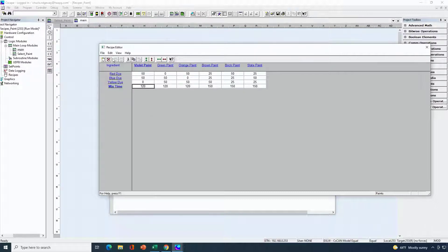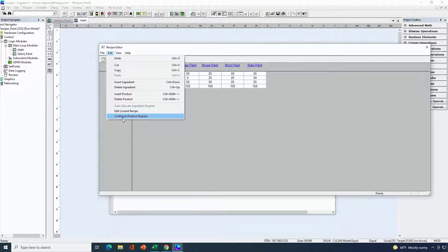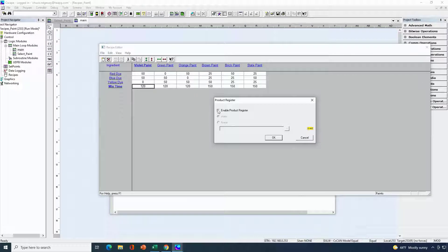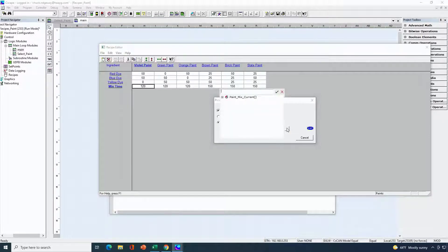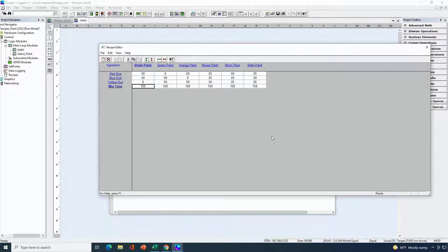One step I did a little out of order — let's go ahead and do that now. After creating our recipe — naming it, sizing it, assigning the file name — another step is to configure our product register. This is the register we can use in logic and on screen to monitor what particular product recipe is currently selected. This can either be numeric as an index, or it can be the ASCII name. I'll go ahead and use name here. I've already created a variable — a byte array that's 32 bytes long called paint mix current — I'll select that one, the first element of that byte array.